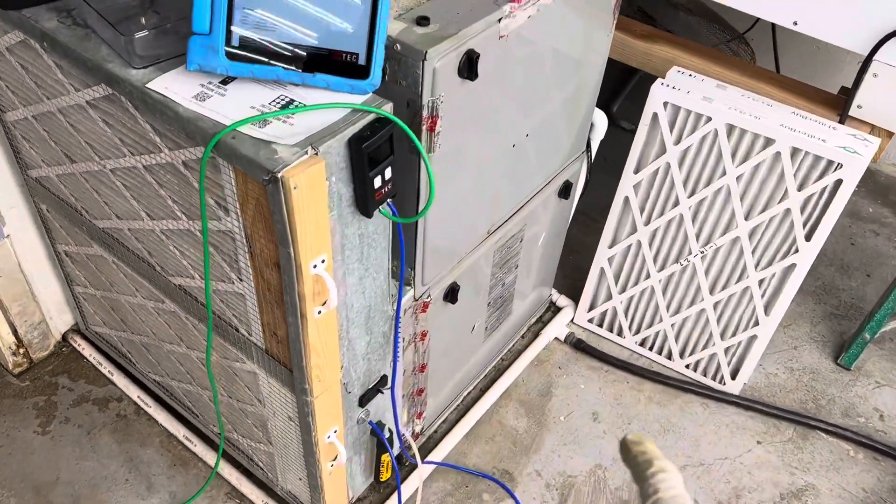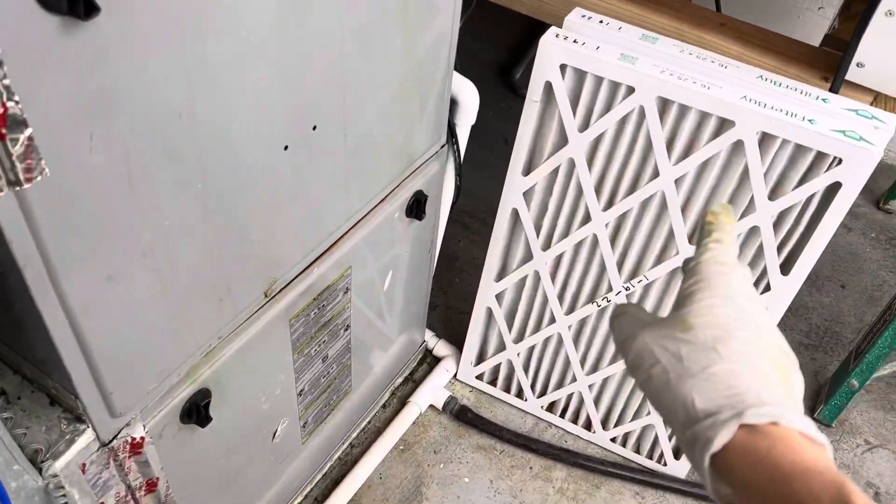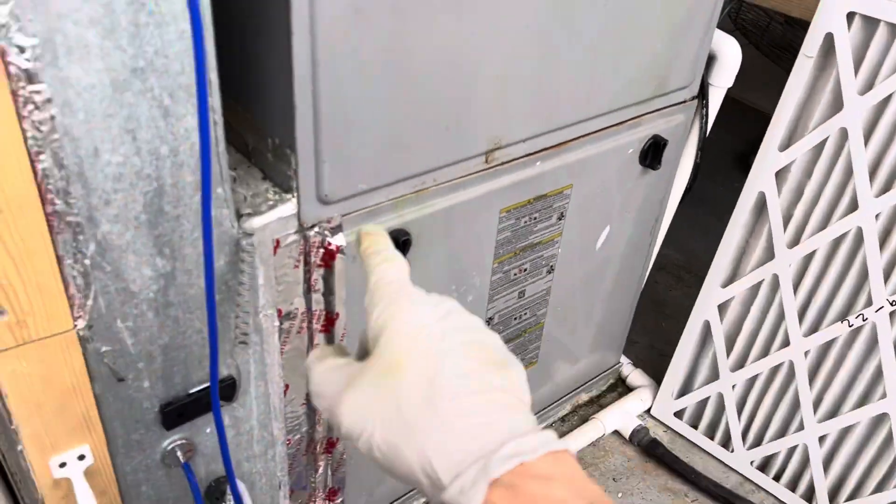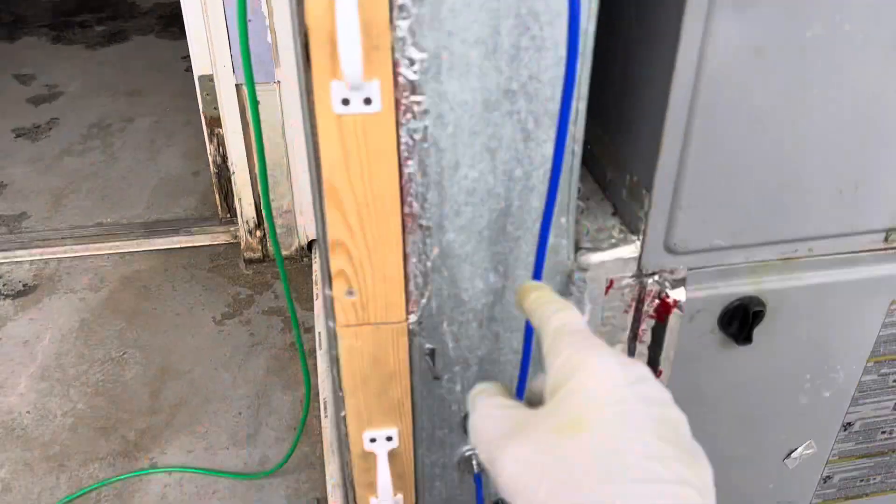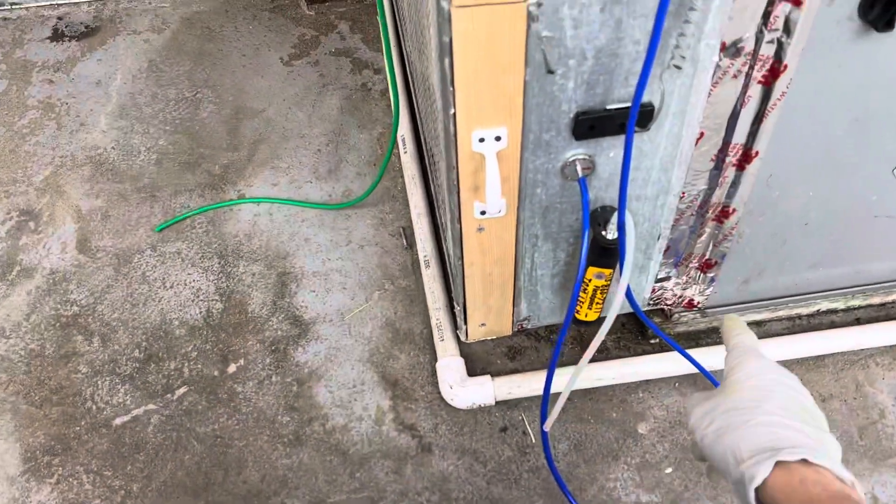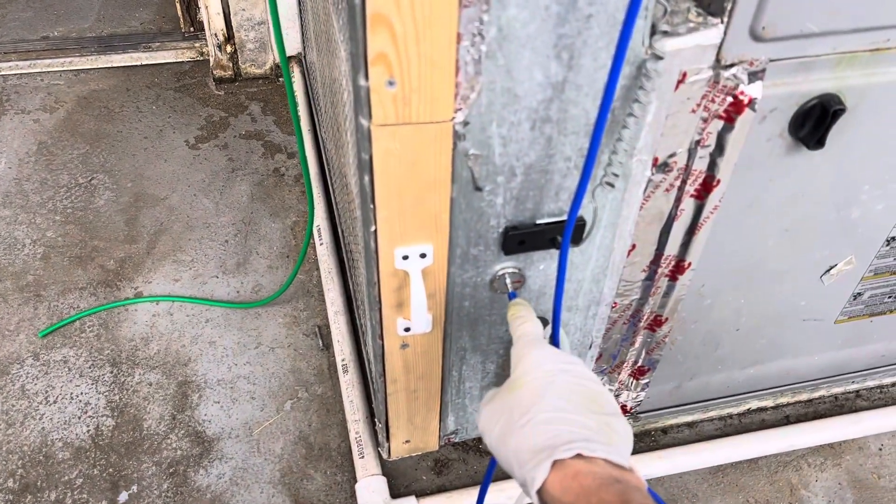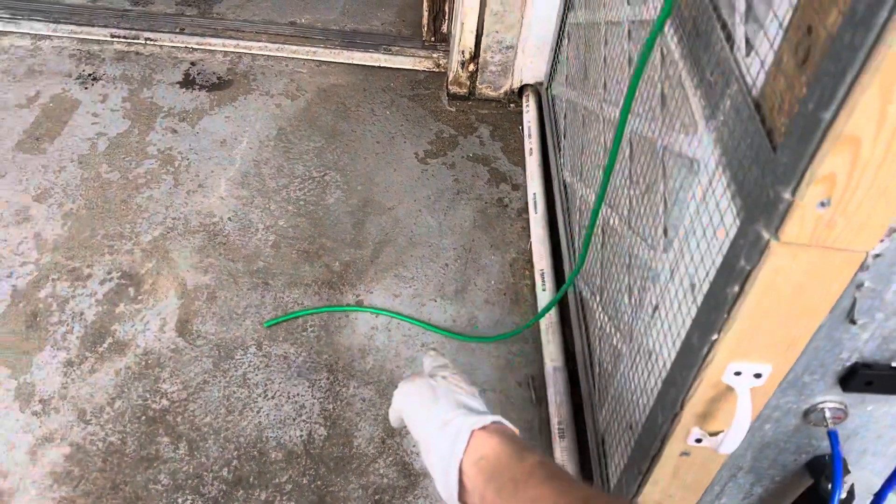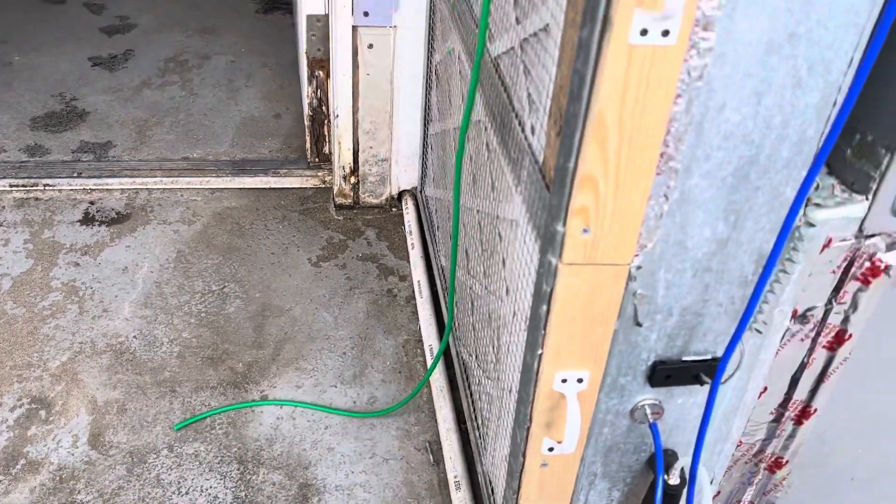Let's do a test. We're putting new filters in place of the old filters while taking the pressure drop across the filter. I'm measuring after the filter and taking my measurement in front of the filter, the drop there.